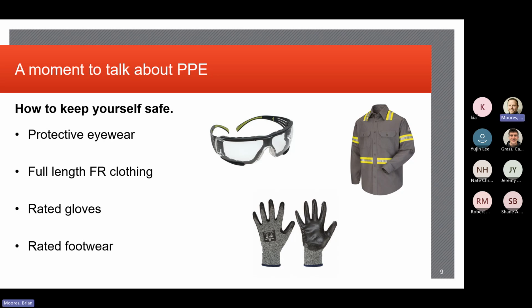Rated gloves, and it's also important to understand that there's a couple different types of ratings for gloves. There's voltage rated gloves and there's arc rated gloves, and they aren't necessarily the same. An arc rated glove will give you arc flash protection, but it may not offer shock protection. A voltage rated glove may have an arc rating. So you've got to be mindful of, if you're just putting on some mechanics gloves that have an arc rating, you could still potentially get a shock hazard there. So something to consider if you start to do some of this kind of work.